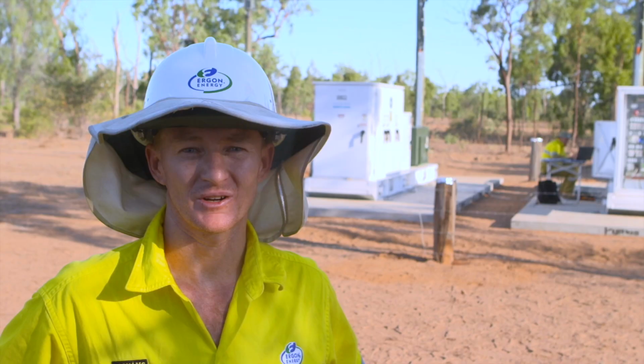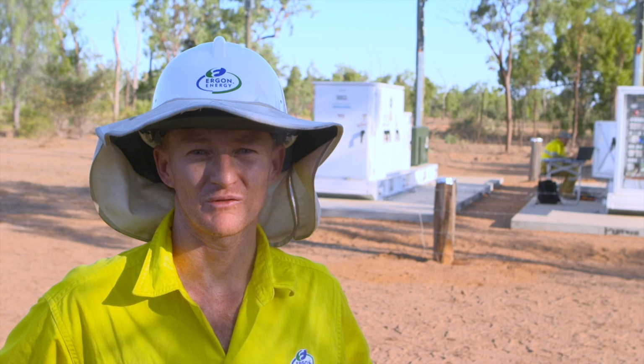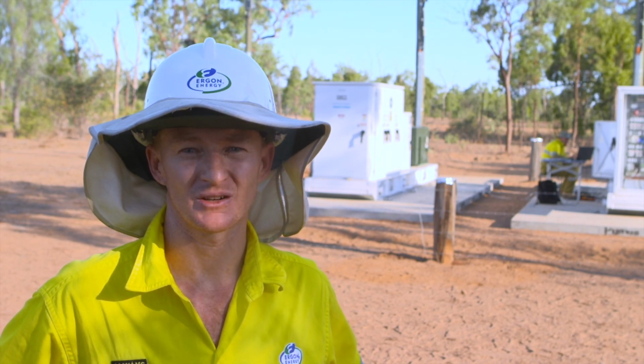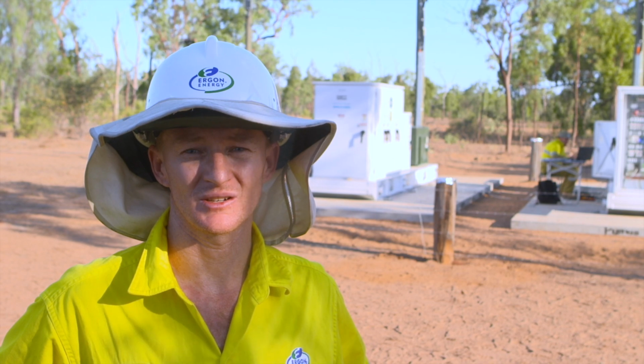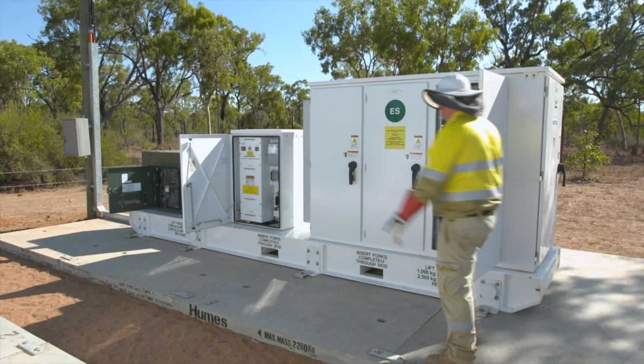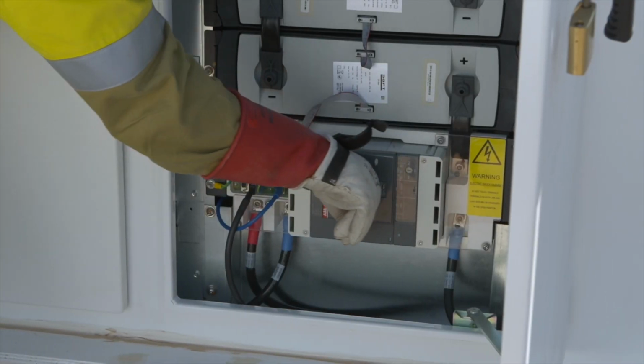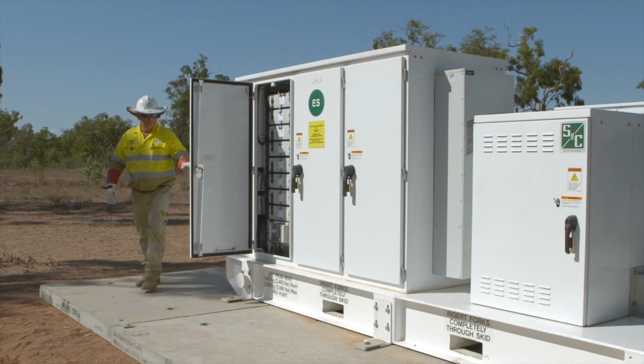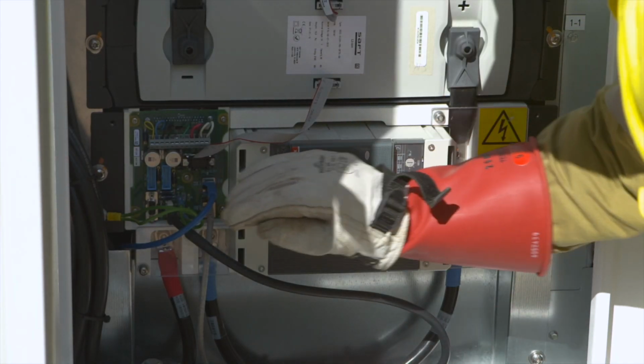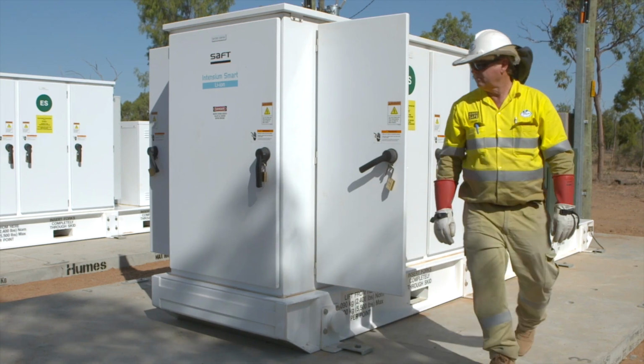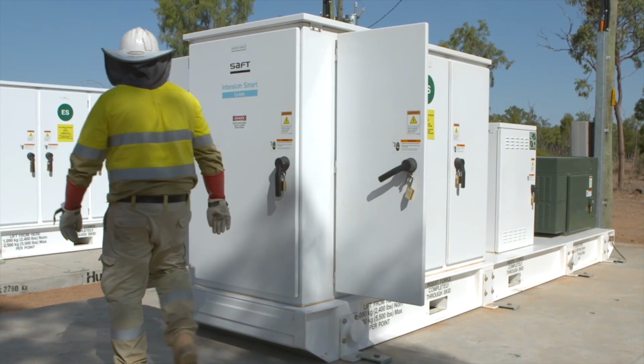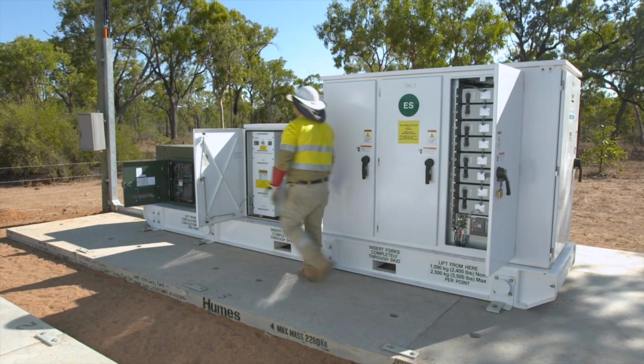After you've completed the work, to restart the unit, turn the inverter back on. Once again, this can only be done under the direction of the GUSS engineer or local SME. Energise string 1 DC circuit breaker in the battery cabinet. Energise string 2 DC circuit breaker in the battery cabinet. Energise the AC main switch in the AC switchboard.